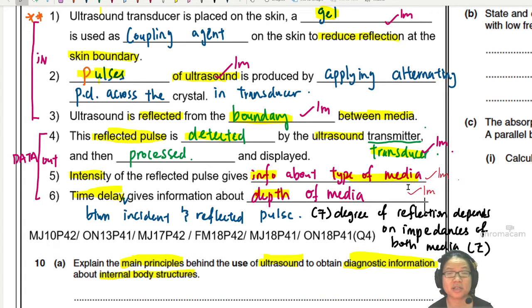Another one that you can write is the seventh one. Degree of reflection. This degree of reflection depends on the impedances of both media, your Z value. Of course, you can write more so that the sentence makes more sense for you and it's easier for you to understand. For example, if I have space, I will say that the fraction of ultrasound reflected depends on the impedances of both media between the boundaries.